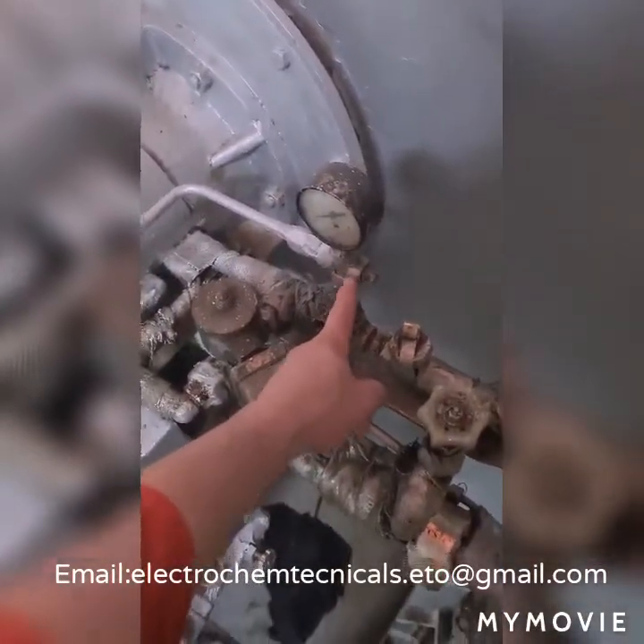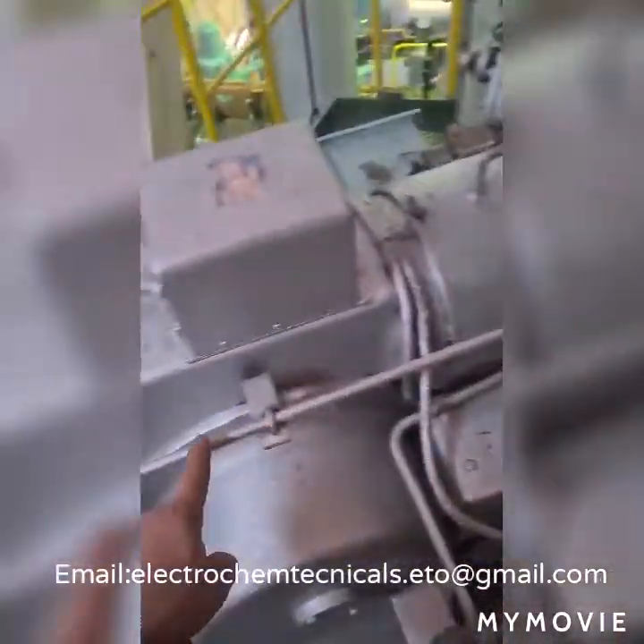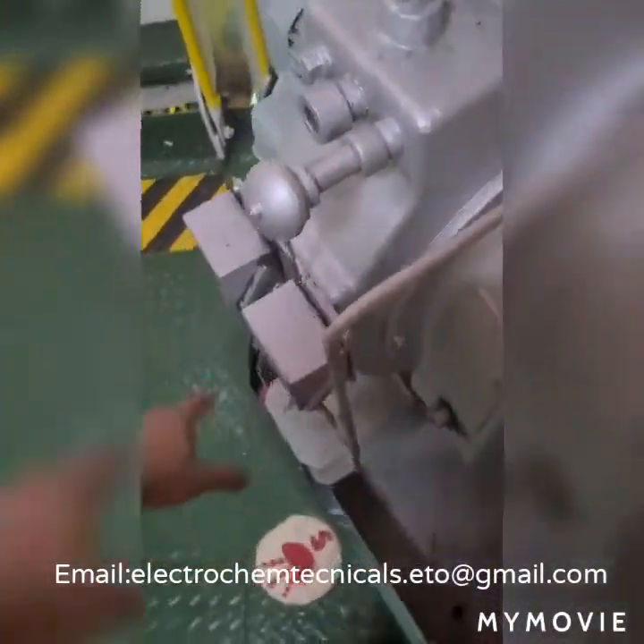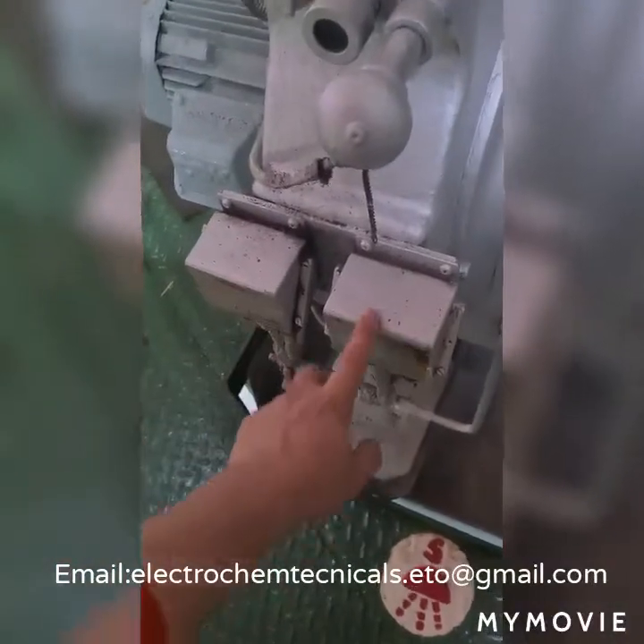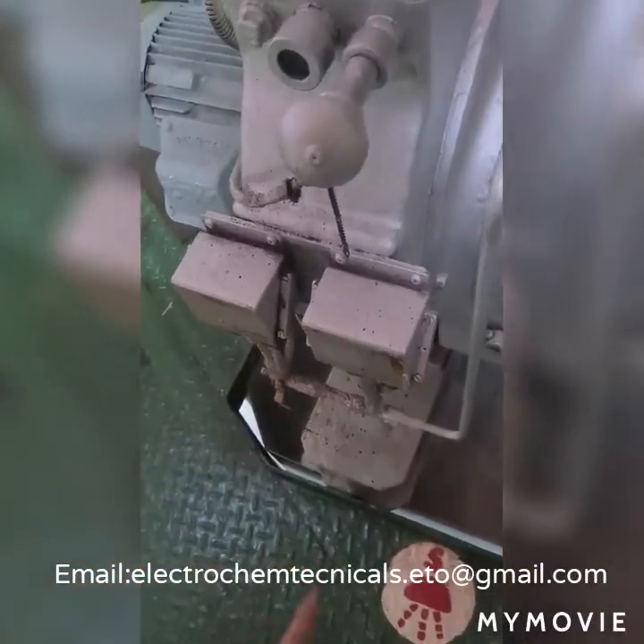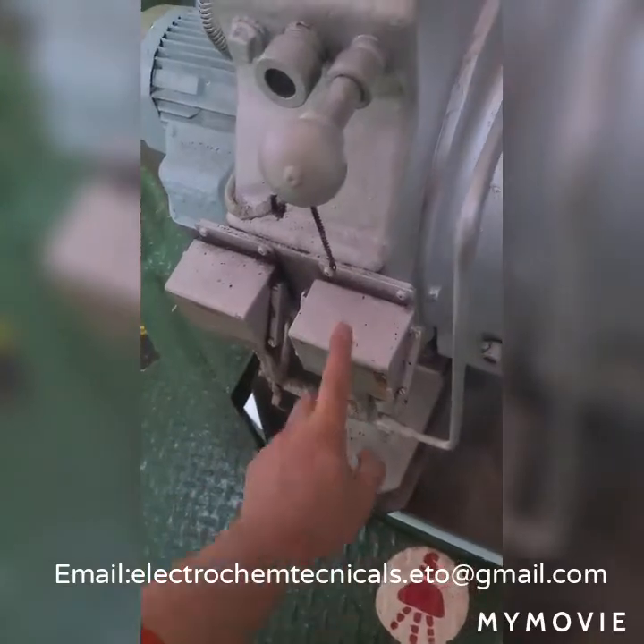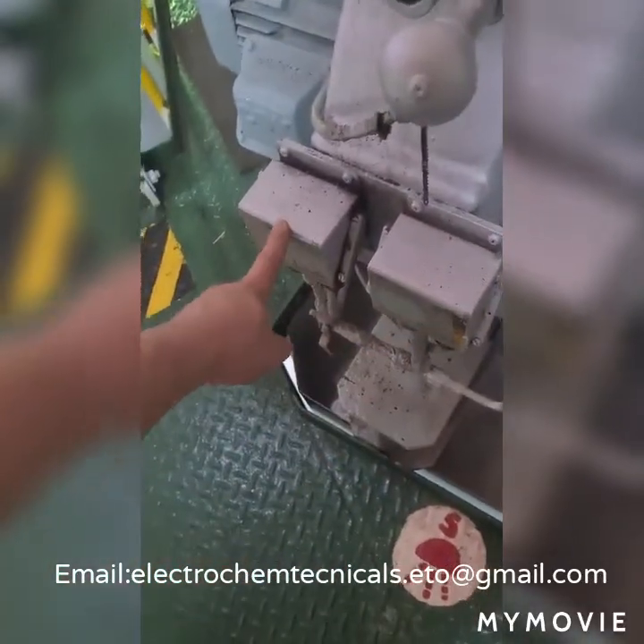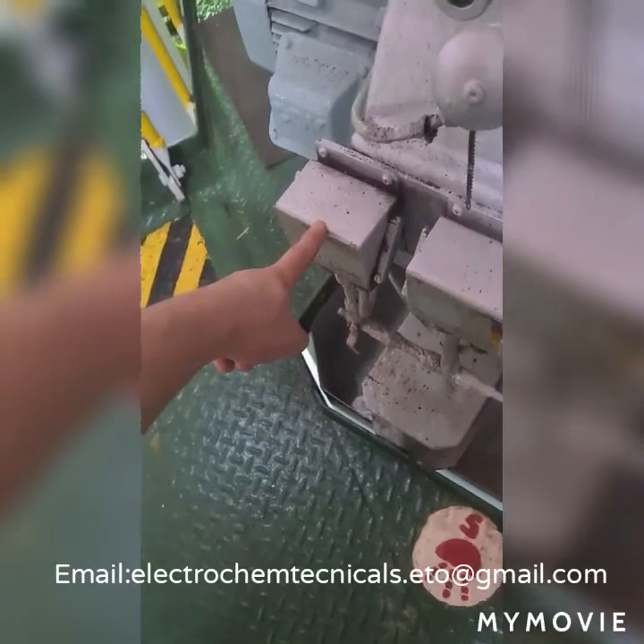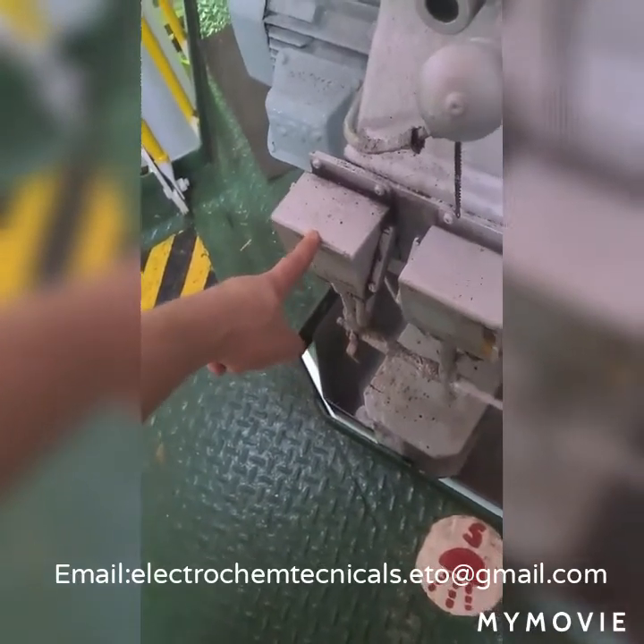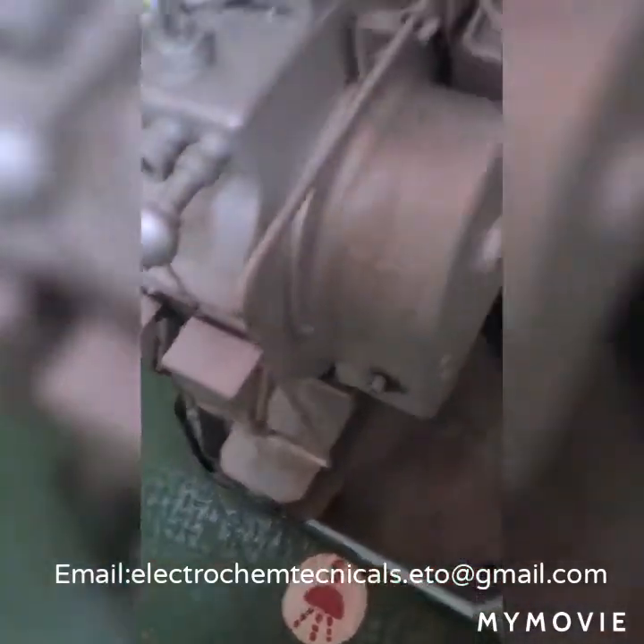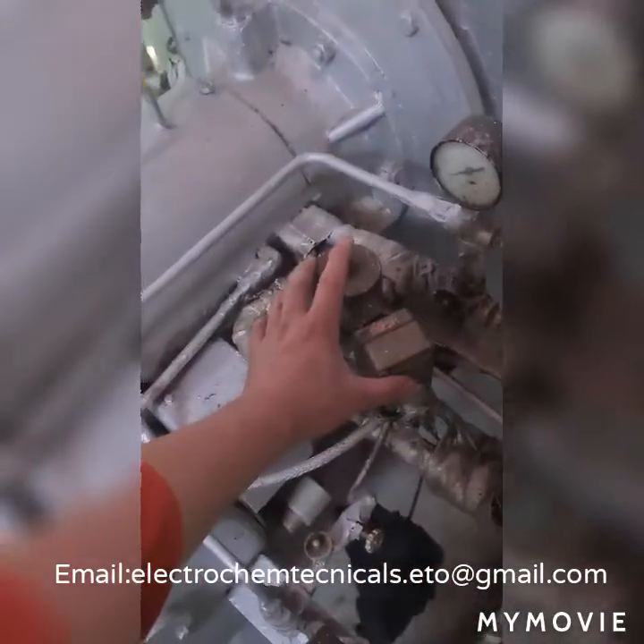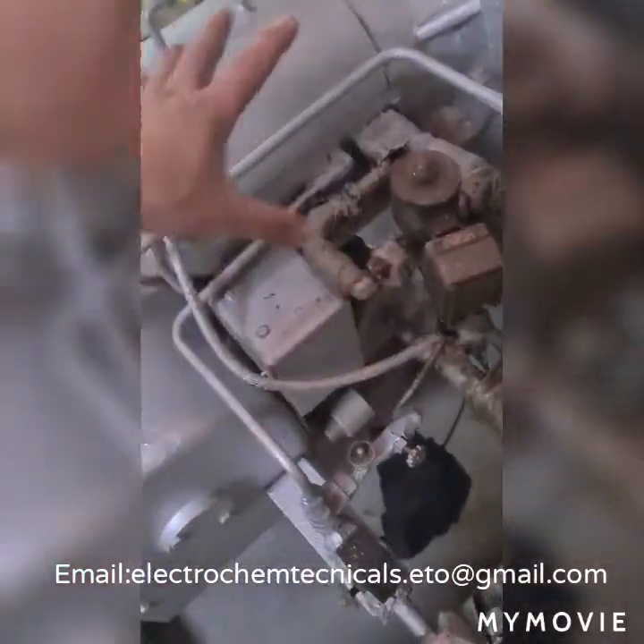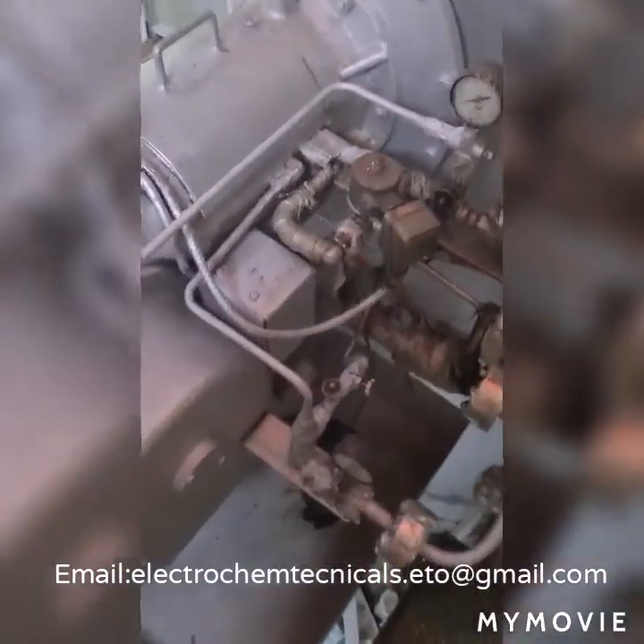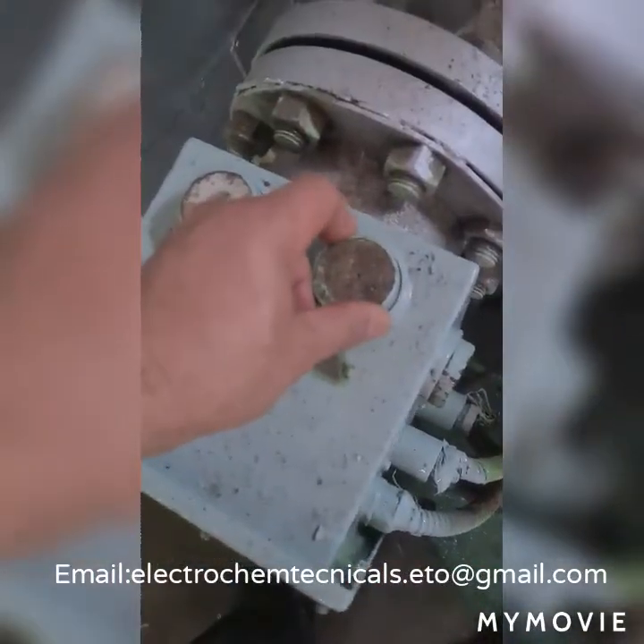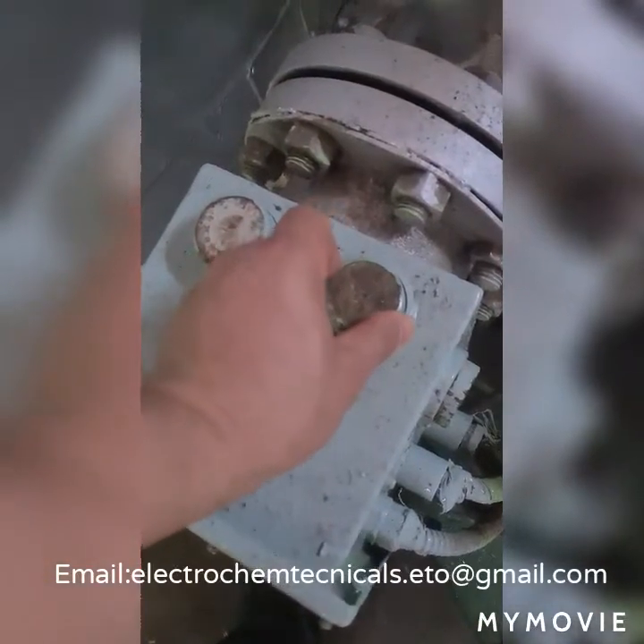This is the pressure gauge. As you will find, there is a pipe going to the two pressure switches. One pressure switch is for low fuel oil inlet pressure, from which the boiler will give a signal to the fuel valve to cut the fuel and stop the boiler from operation. And this is the high temperature fuel inlet alarm monitor.